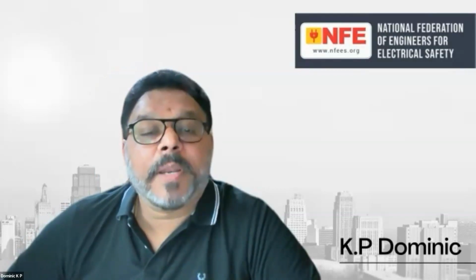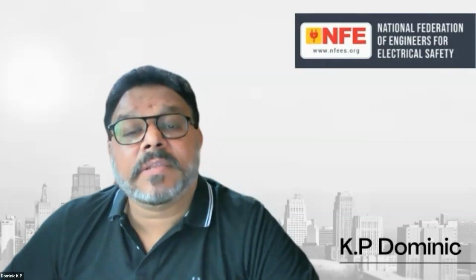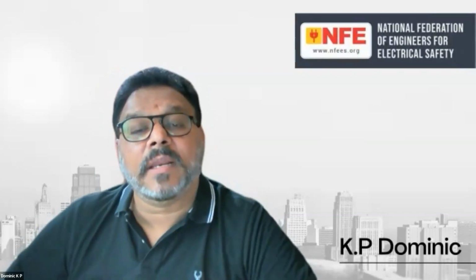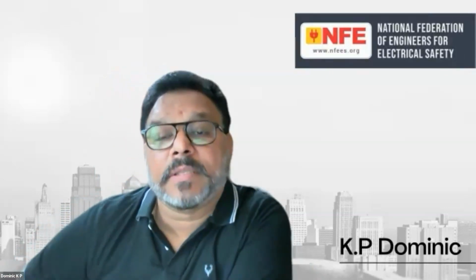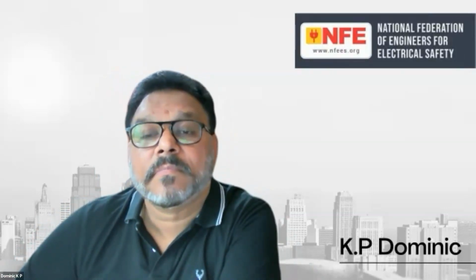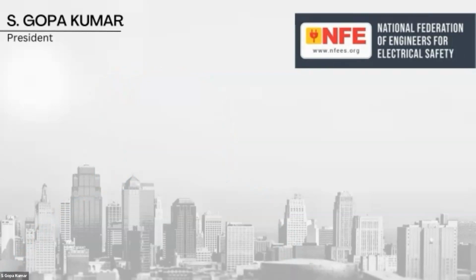Prem Kumar asks, can electrical earthing and LPS have a common earthing system? Of course, yes. The down conductor and the MET must be bonded, and the SPDs have to be installed on the main incoming panel. Then only is lightning protection complete. If this is not carried out, you cannot claim your lightning protection is complete.